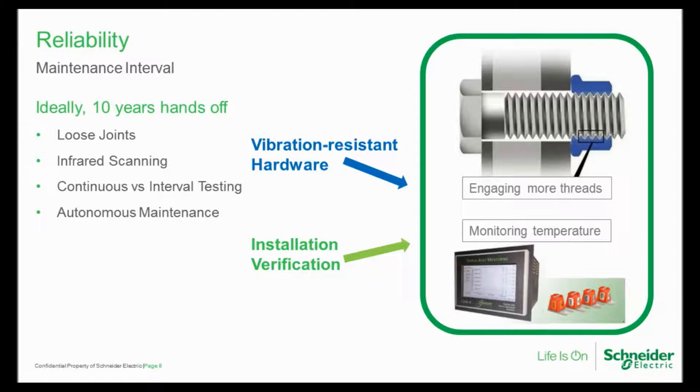This is a major development. In cases where we're not sure the joint stays tight, there are monitoring systems. The lower image shows a system that monitors assets especially at critical joints and hotspots. The small orange sensors use several different technologies and offer battery-less, wireless monitoring of joints. Inside the enclosure, an antenna sends a signal through the air to the sensor, which receives it, processes it, and sends it back — without any wire and without any battery — giving us interpretation of what's happening at the joint. Over time we can watch trends in our most critical spots.